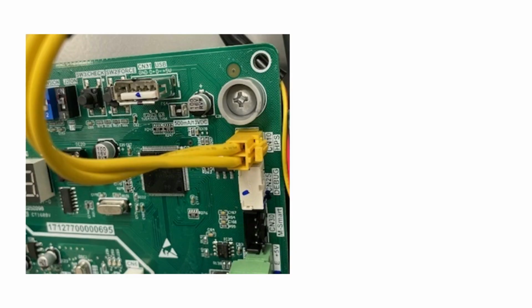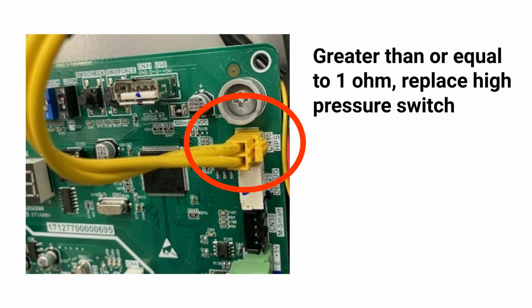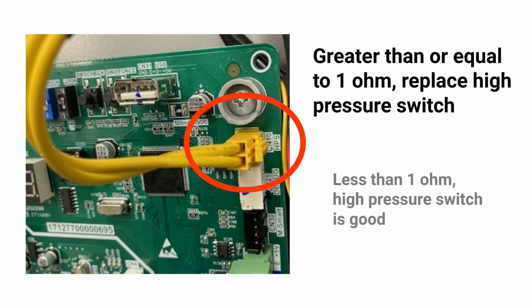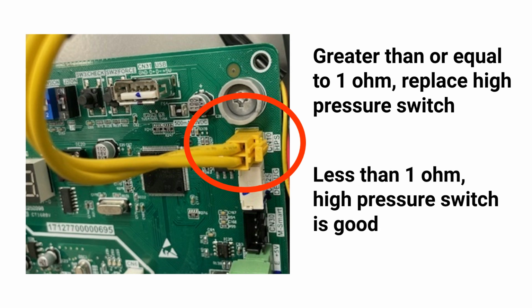The component that is related to a P1 or F1 error code is the high pressure switch. To check the high pressure switch, locate the yellow Molex with two yellow wires in the upper right of the control board marked CN10. Unplug the Molex and set your meter to ohms. If the resistance is greater than or equal to 1 ohm, replace the high pressure switch. If the resistance is less than 1 ohm, the high pressure switch is good, and further investigation of the refrigerant cycle is required. For more information, visit our other troubleshooting videos.